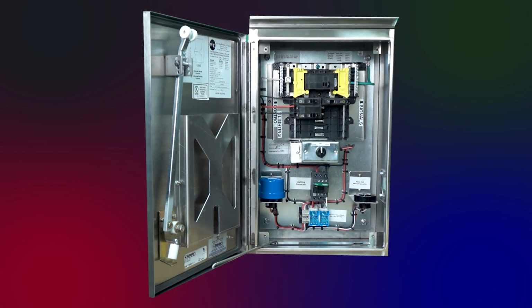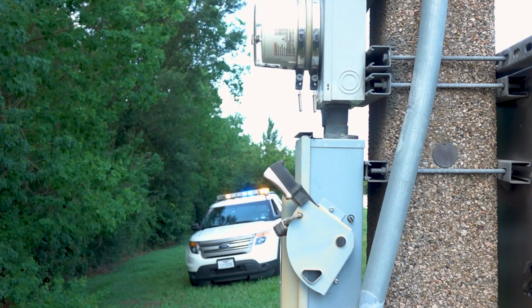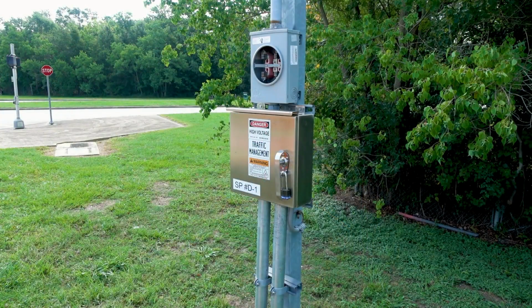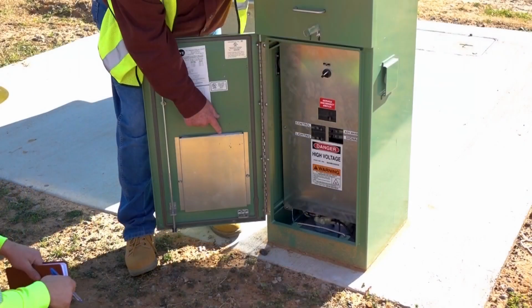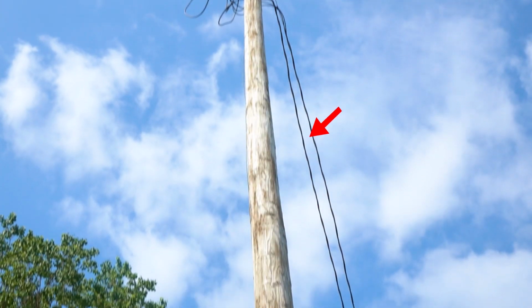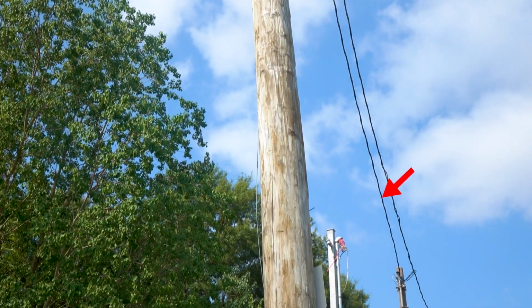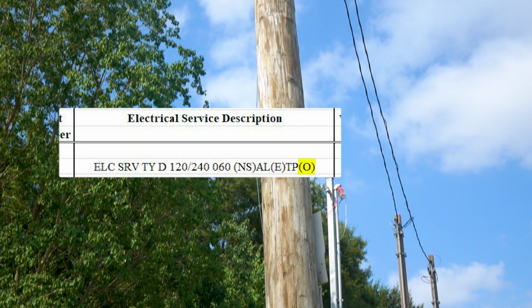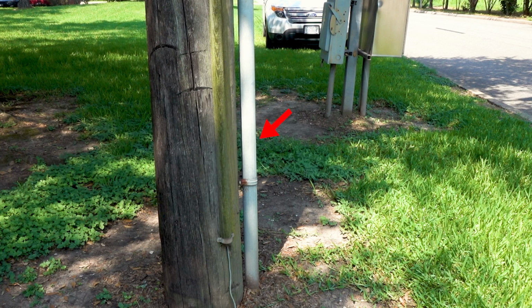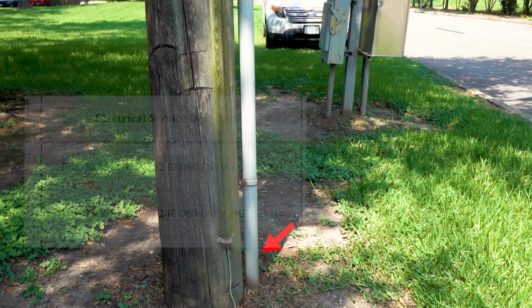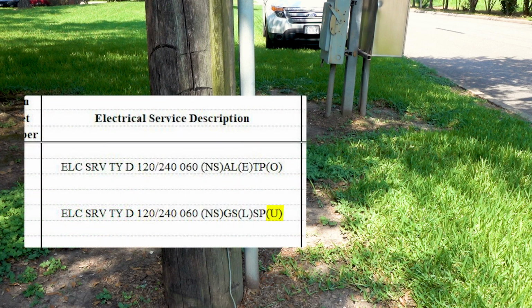The type of electrical service is independent of the support structure it is mounted on. Electrical service equipment can be supported by either a timber pole, granite concrete pole, steel frame, or a pedestal enclosure on a concrete foundation. Some electrical services are connected to overhead service drop conductors, designated by the letter O in the service descriptive code. Other electrical services may be connected to underground service lateral conductors, designated by the letter U in the service descriptive code.